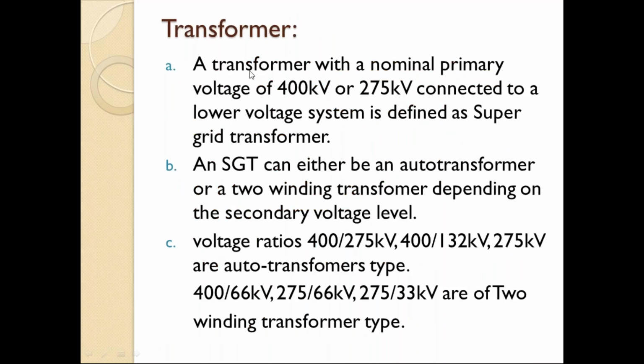As I told, for transformers we are using three types of voltages: 400 kV, 275 kV, and 132 kV. But in India, it is 400 or 220 kV and 110 kV. We are using SGT, supergrid transformers. In the UK, 400 kV and 275 kV substations use supergrid transformers for these two voltages. The ratios are 400/275, 400/132, 275/66, and 275/132.